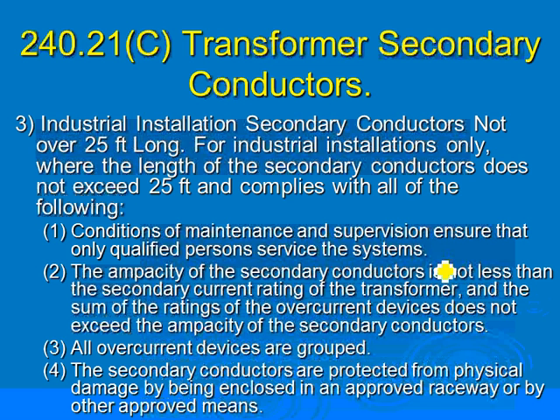Transformer secondary conductors. This talks, guys, about the 25-foot rule for industrial secondary conductors, not over 25. Here are the rules for them. Conditions: first of all, we are in an industrial installation, with only qualified people like yourselves working on the system. The ampacity of the secondary conductor is not less than the overcurrent protection device at the end of it. All overcurrent protection devices are grouped. The secondary conductors are protected from physical damage.